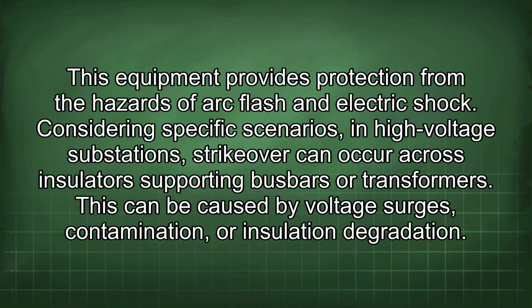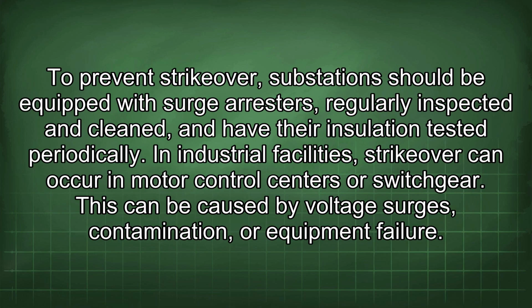Considering specific scenarios, in high-voltage substations, strikeover can occur across insulators supporting busbars or transformers. This can be caused by voltage surges, contamination, or insulation degradation. To prevent strikeover, substations should be equipped with surge arresters, regularly inspected and cleaned, and have their insulation tested periodically. In industrial facilities, strikeover can occur in motor control centers or switchgear. This can be caused by voltage surges, contamination, or equipment failure.